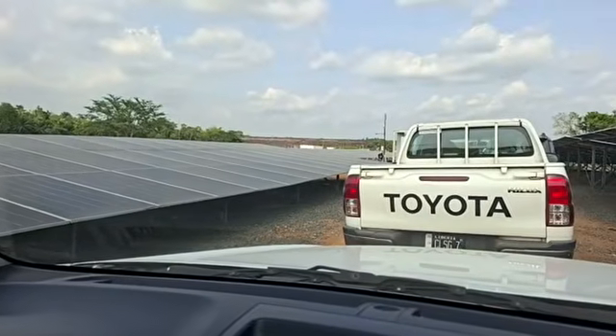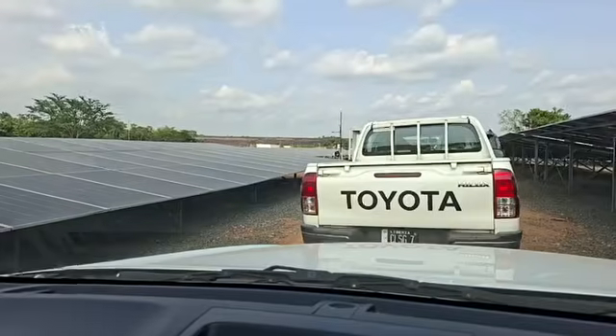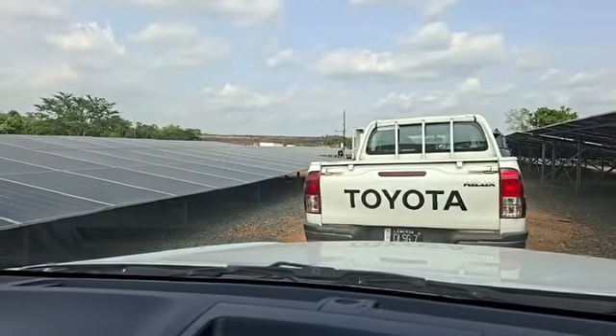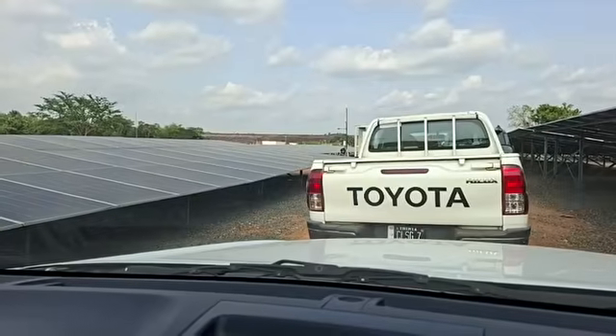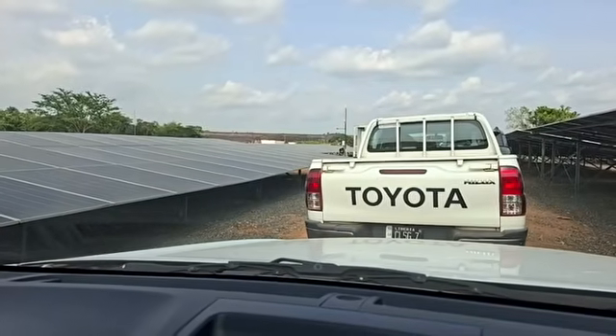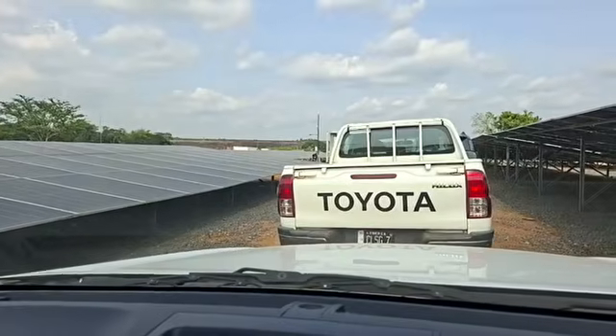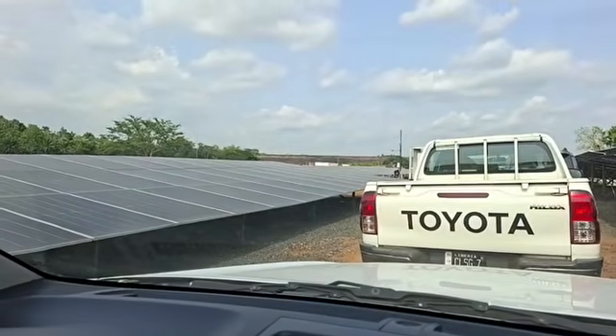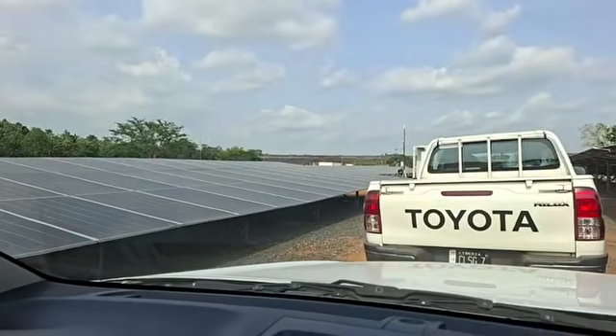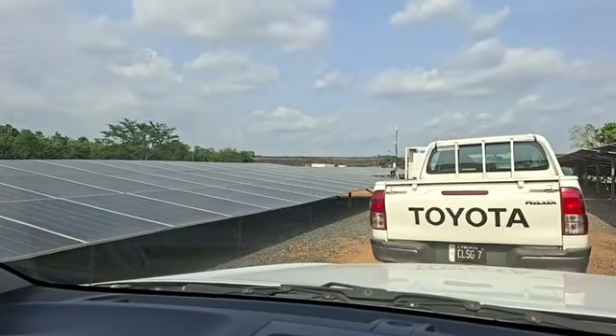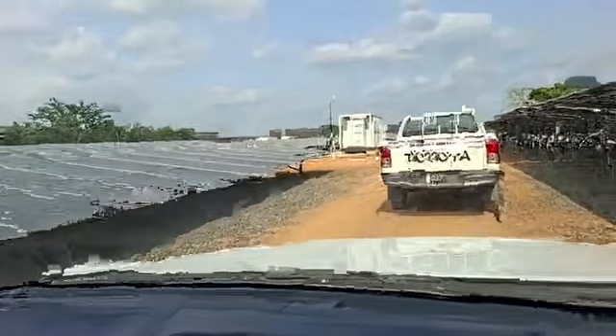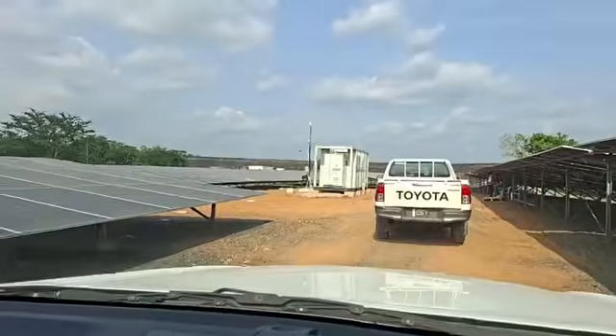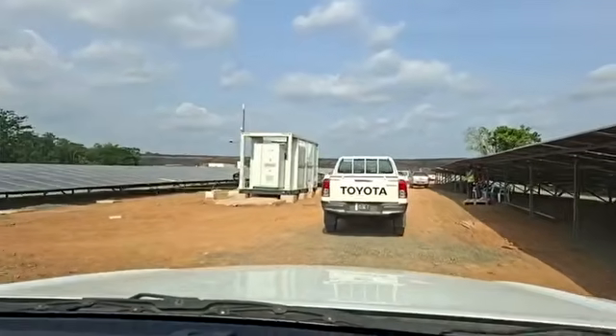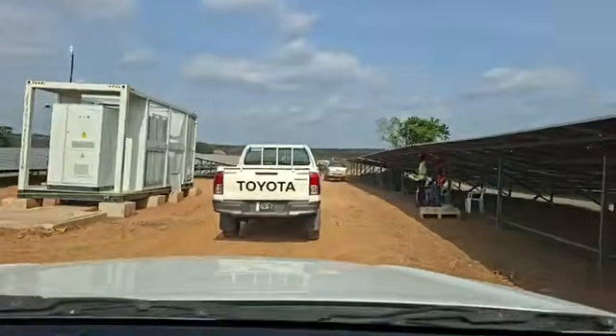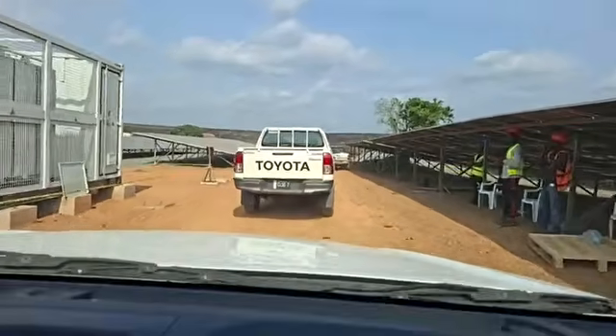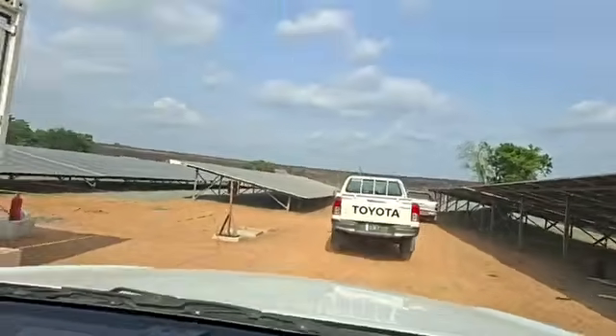And today is a joint inspection team here as the commissioning of this 20 megawatt solar farm gears up, anytime very soon, and as part of the activity of the commissioning, there is this joint inspection. And now, as you can see, the plant is being turned on, being monitored for about 24 hours. And in the next 1-2 days, they are going to inject power and then evacuate power to the powerhouse as part of the testing activities. It's going to take a few days, possibly a week, to ensure that all of the technical works are in line, quality assurance, health and safety, environment, and everything.